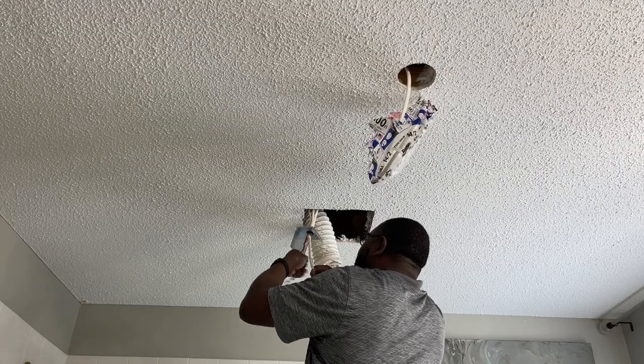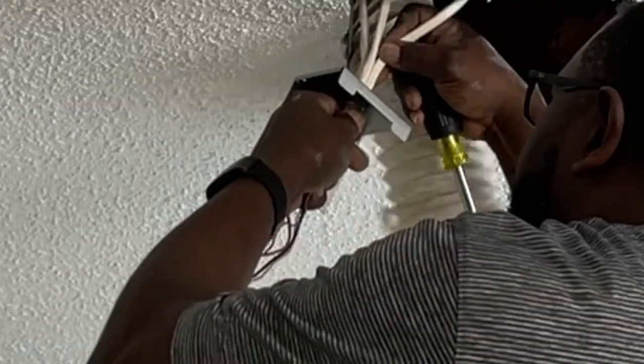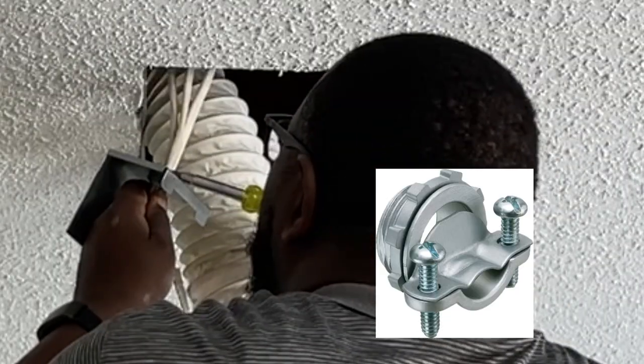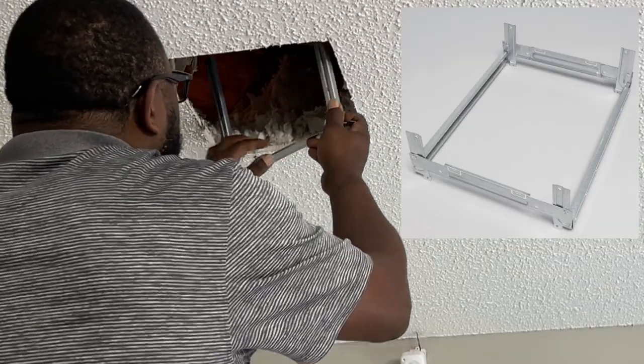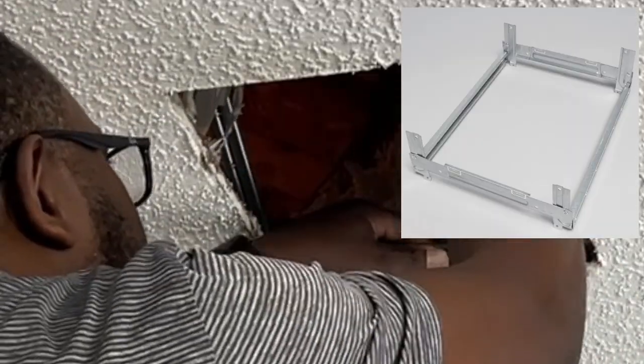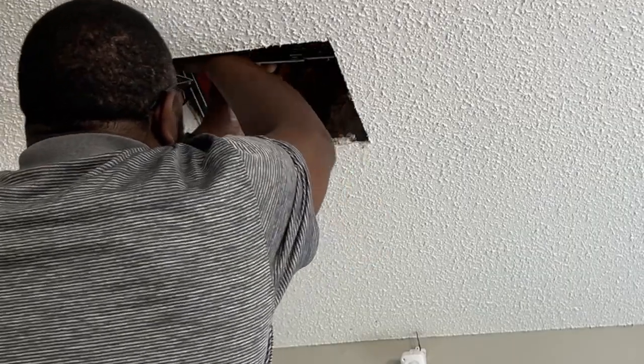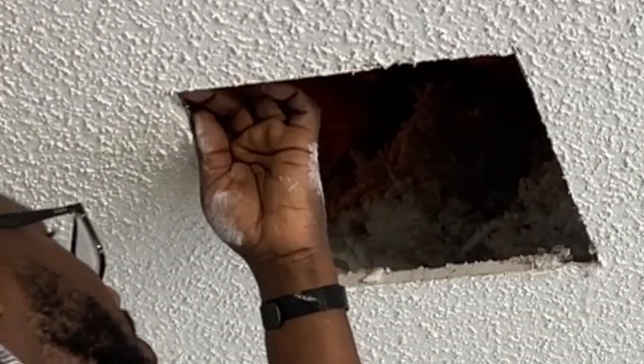As you can see I've already ran some 14/2 Romex from the new light location through the Romex connector to the electrical box. The provided bracket is designed to go joist to joist and the only thing you have to do is just screw it in on either side.